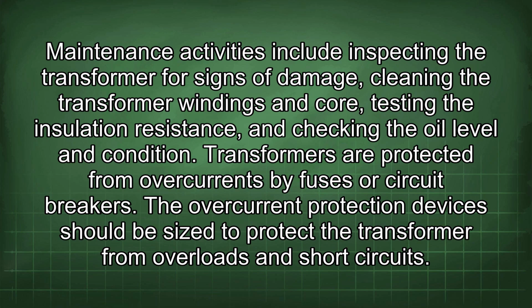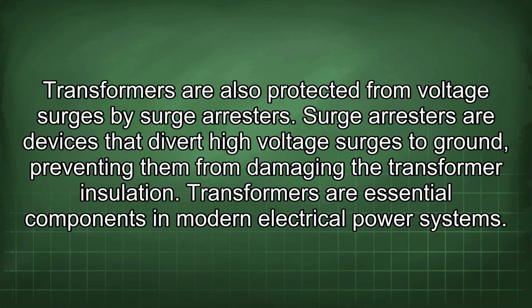Transformers are protected from overcurrents by fuses or circuit breakers. The overcurrent protection devices should be sized to protect the transformer from overloads and short circuits. Transformers are also protected from voltage surges by surge arresters. Surge arresters are devices that divert high voltage surges to ground, preventing them from damaging the transformer insulation.